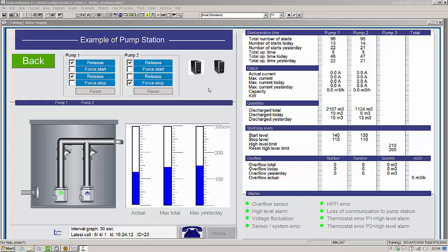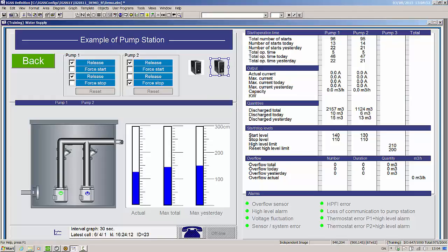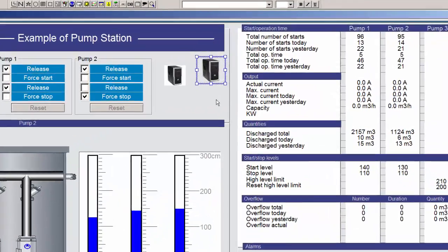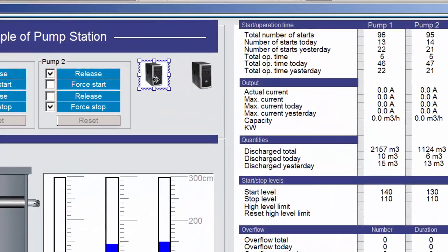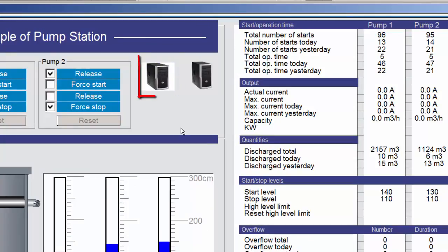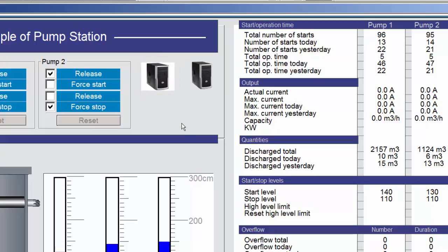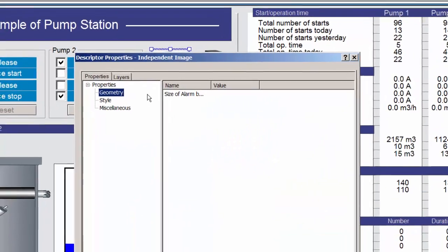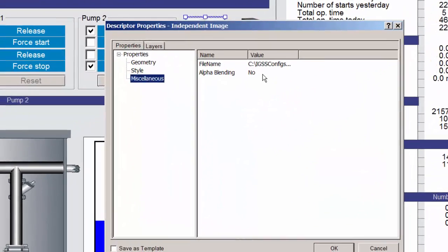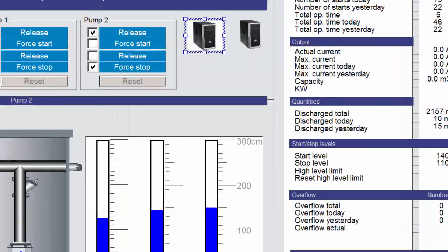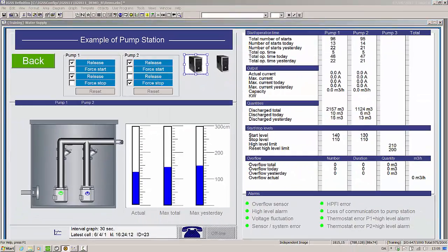We have introduced transparency properties for some descriptors in IGSS 11, for example images. This image is taken from the demo configuration, but the background has been made transparent in another program. You can, for example, use Photoshop or GIMP to do this. This is the original image, and as you can see, the transparent image blends better with the diagram background. You must remember to enable transparency for the image in the image properties. In this case, the transparency called alpha blending has been disabled.